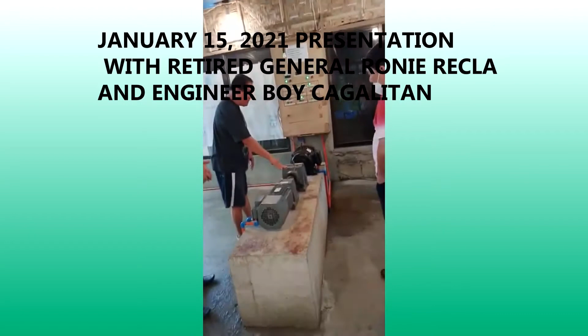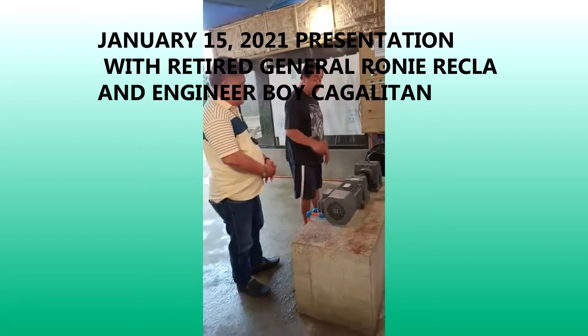So this is the only reason why I'm using the 2 gearboxes. This second gearbox is to transform the speed to drive the 12 kilowatts, because if this 2.2 kilowatts we direct couple it to the 12 kilowatts, it cannot overcome it. There's no circumstance where it won't trip.